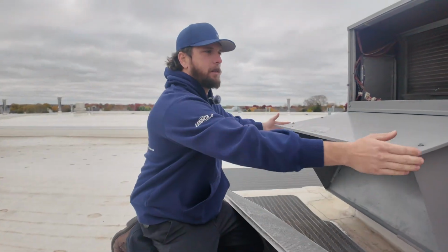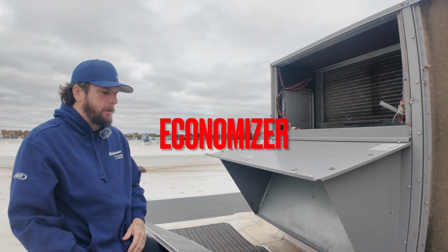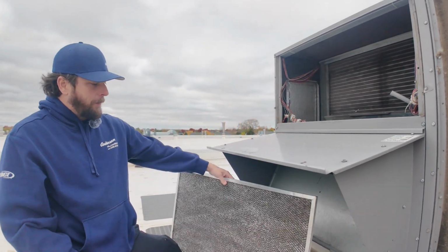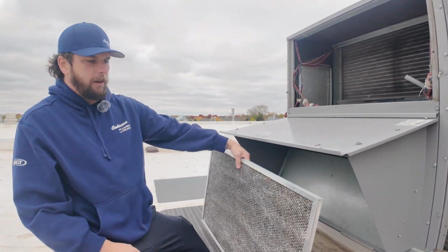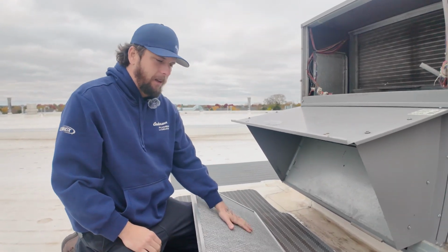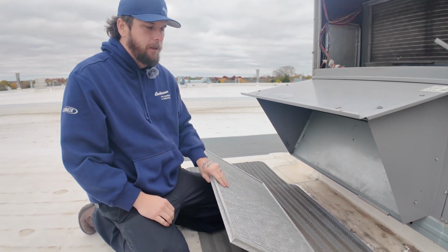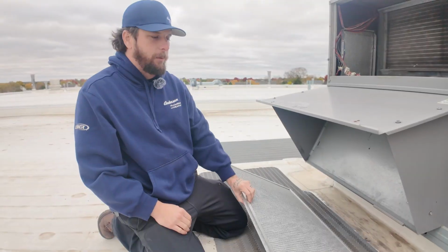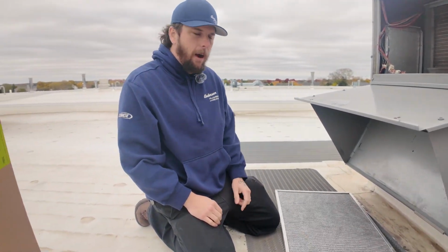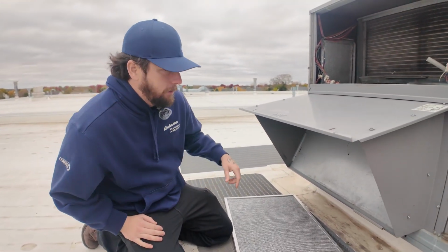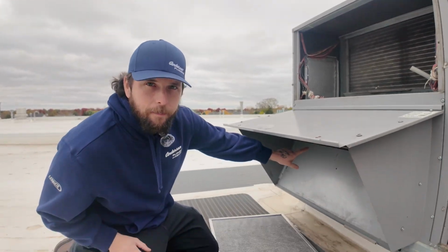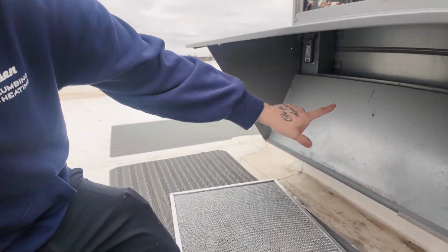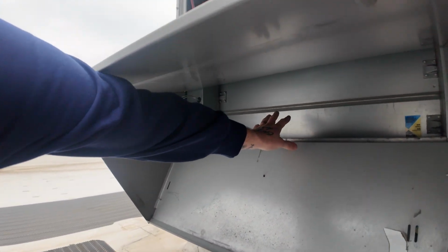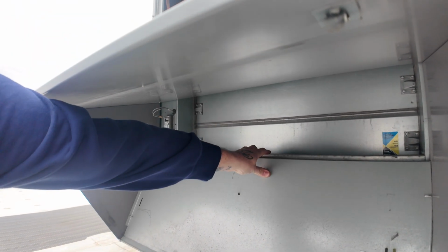Right here, just this portion hanging off of the rooftop unit is what's called an economizer. The economizer does have its own filter. It's not something that really has to be replaced unless it's damaged, because it's an all aluminum filter. Basically, we just flip it on its back like this and hose it out. What an economizer does is, if you look in here, there's two flaps. These flaps will open up under certain conditions.